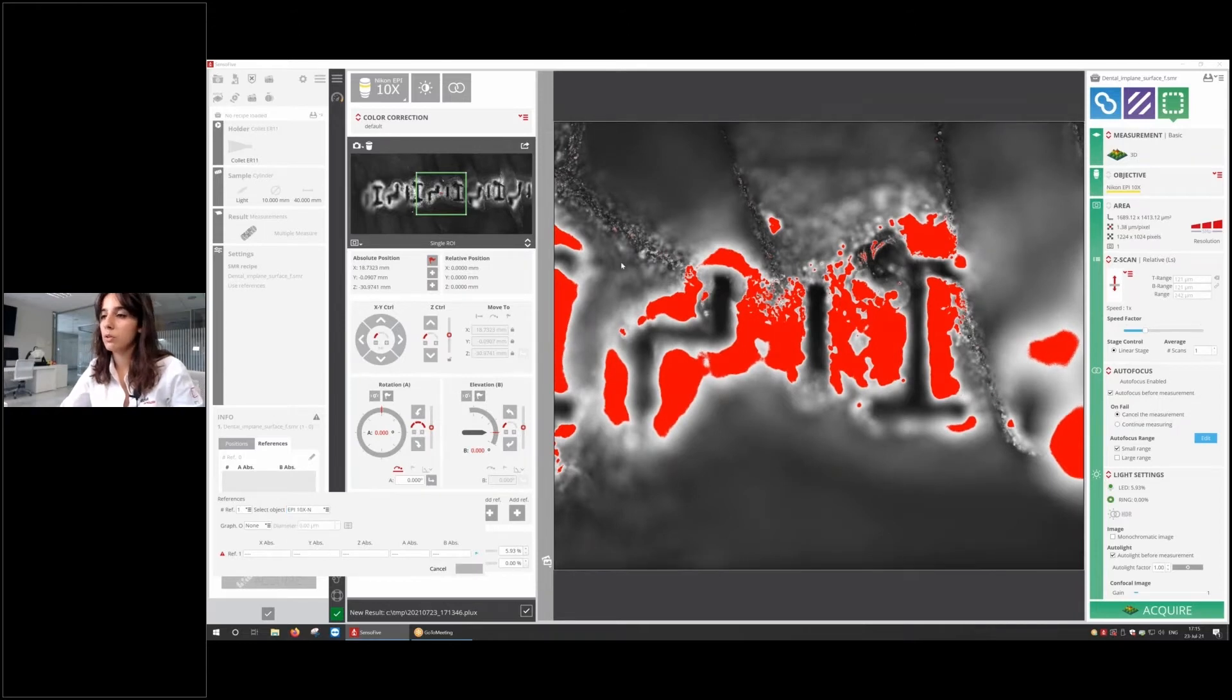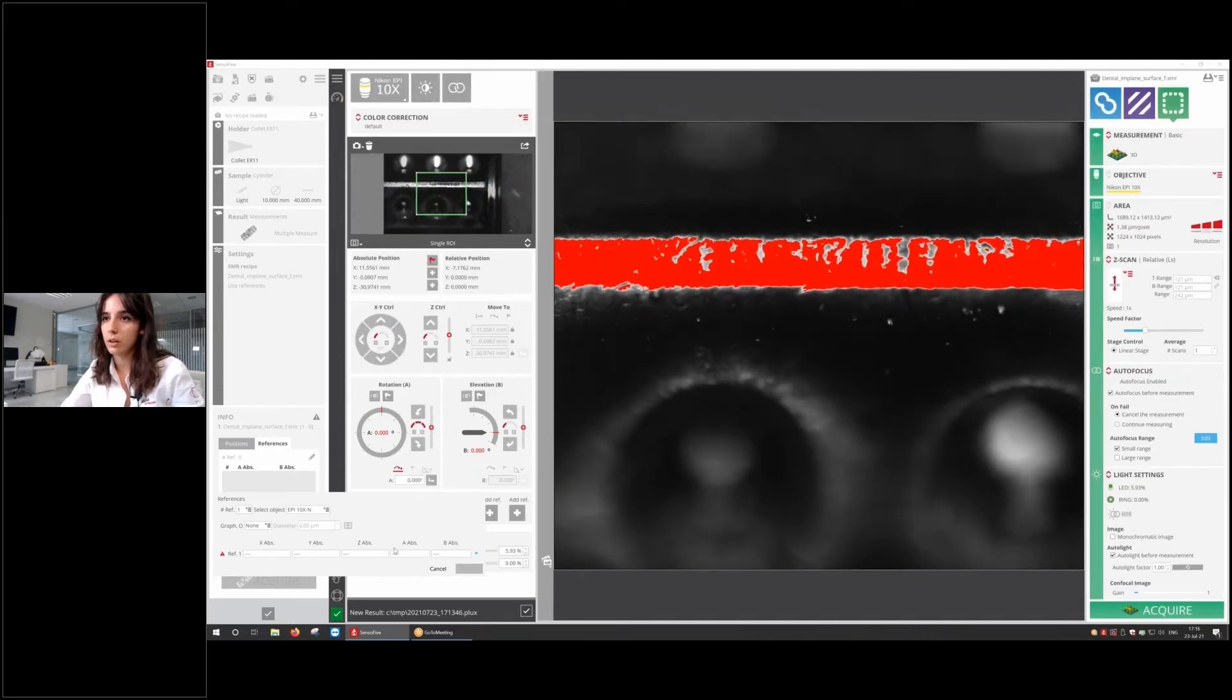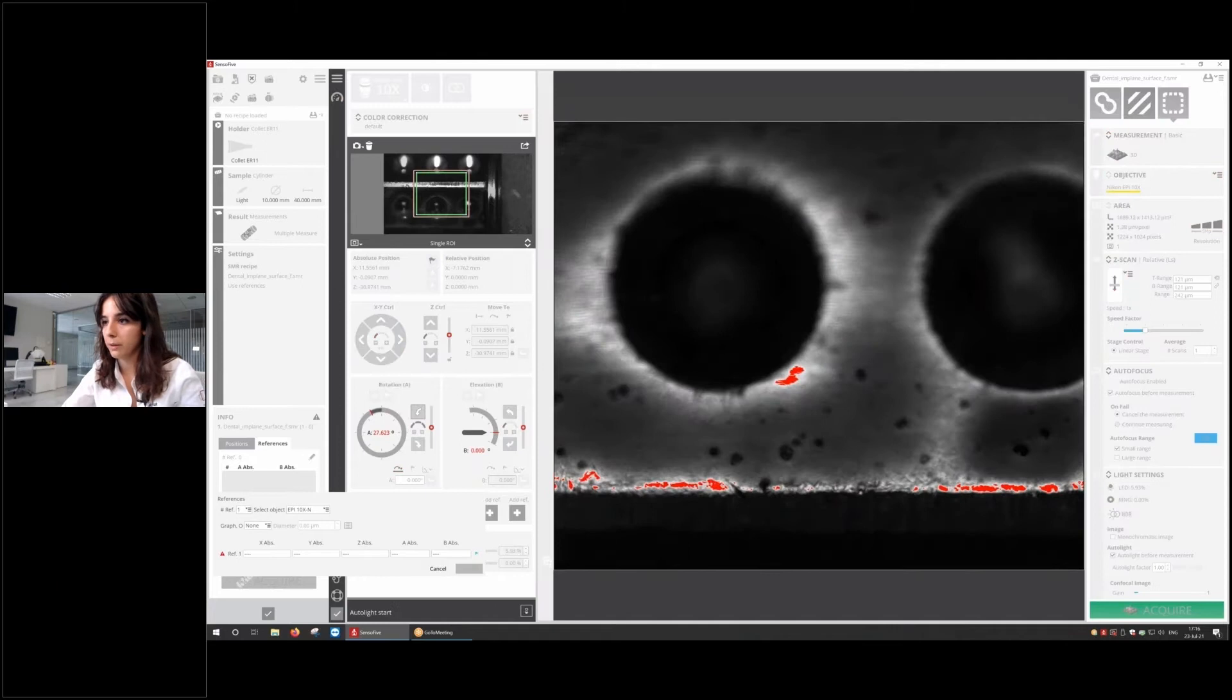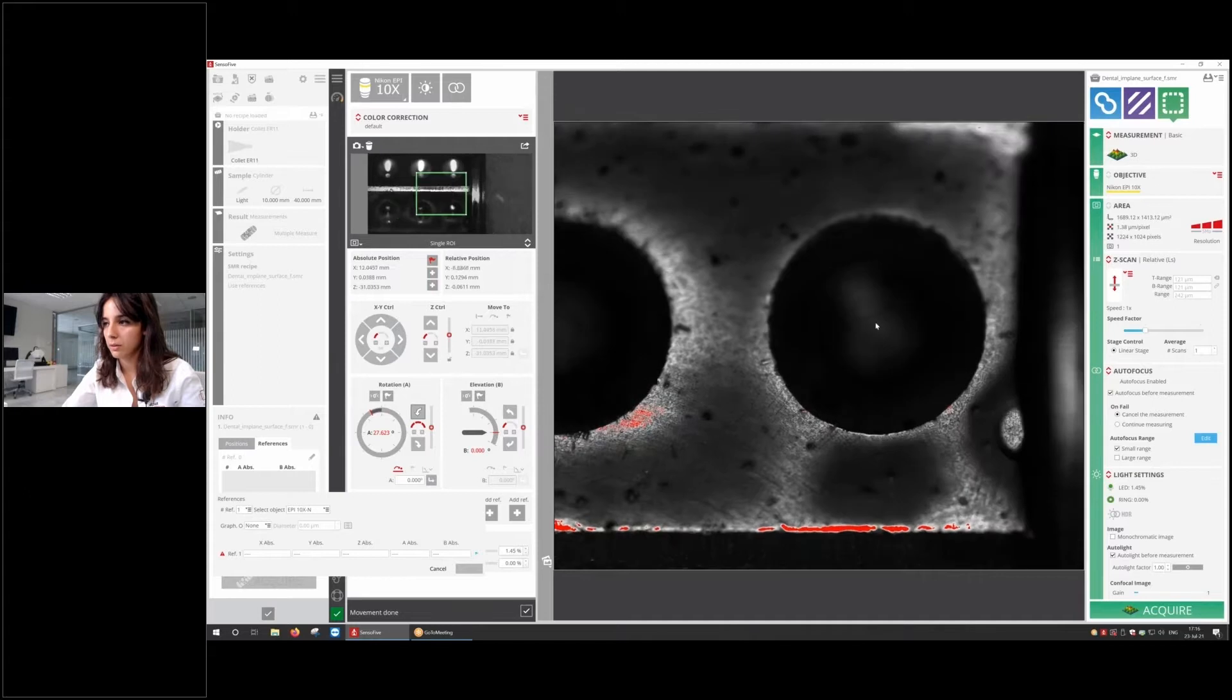To establish references, I can select how many references I want, one, two, or three. Normally, it's better to use as many as possible because you're going to fix more degrees of freedom. In this case, I'm going to use one because I just want to demonstrate it, and I'm going to use a 10x. I'm going to tell the software, and what I'm going to use for referencing is a chamfer and some features on the chamfer. These features here, these circles, are found in several places of the chamfer, so I marked some. Let's go and find them. This is the one, and you see that this has some shadowing here, so we're going to use the first one.